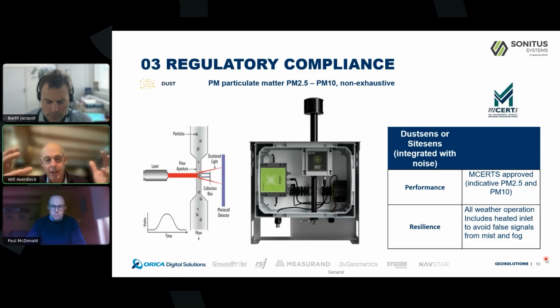So air is taken in, is heated, and then it moves through the optical particle counting where it is sized and dust concentration is assessed, and then it communicates via 4G, 5G into the cloud. This particular instrument is the Dustsens. As Bart referred to earlier, we have a version where there's a noise monitor integrated with that, which is our Sitesens, and both these systems have an MCERTS approval for indicative monitoring of PM2.5 and PM10, which is the appropriate standard for industrial and construction site monitoring. But resilience and robustness is really important with particulate monitoring. Particulate contaminates, water vapor is an interferent, and dealing with this in a robust way is very important. This is what we do with these instruments as well.